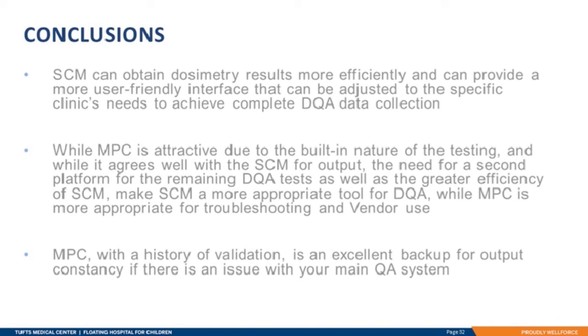In conclusion, the SunCHECK machine provides a more efficient, customizable, and applicable platform for daily QA compared to machine performance check when all of the recommended daily QA tests are considered. Machine performance check, on the other hand, is a great resource for troubleshooting. The agreement between the two platforms for output constancy is impressive, and if properly vetted against an independent QA system, would make for an excellent backup in case of hardware or software issues with your main QA platform.